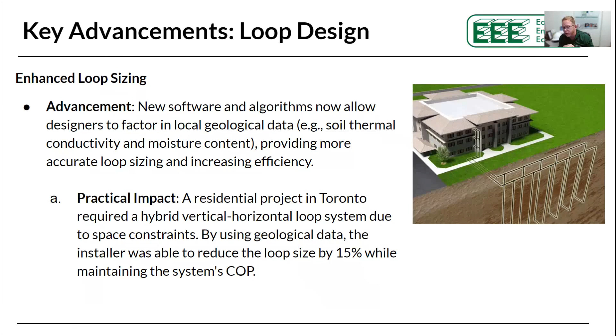Now this is mainly on the commercial side. Commercial I'd deem to be anything that's a large residential application or a high-rise building. The ability for us to go and do a TRT test means that we can see, from a thermal conductivity standpoint, how many watts we can pull out of that ground loop for every degree of change.